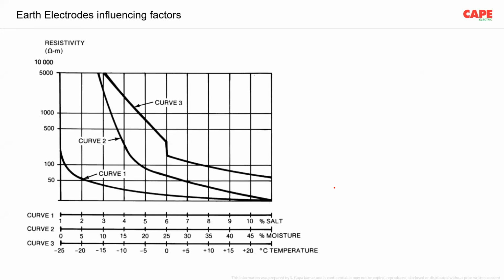This particular table is actually derived from IEEE 80, which explains the effect of temperature, moisture, and salt in a typical case. On the left side, you can see the soil resistivity. Curve number 3 is for temperature, curve number 2 is moisture, and curve number 1 is salt. More than the salt, moisture matters: if the soil doesn't have moisture, of course, the value is too high. If the temperature is minus, then the problem is even higher.